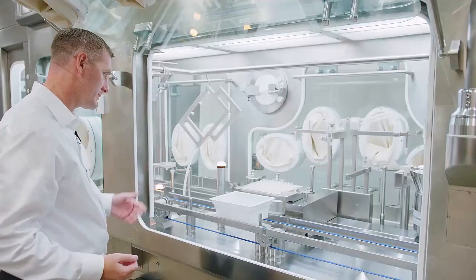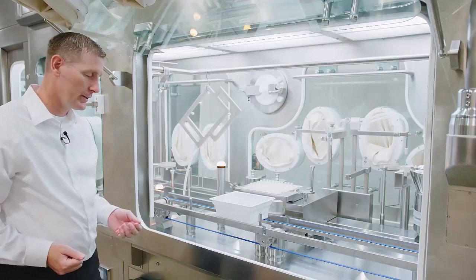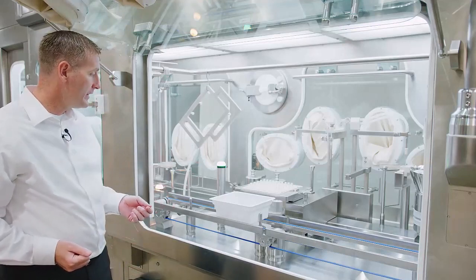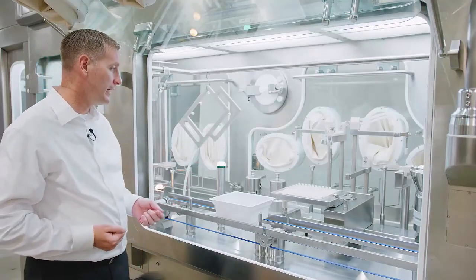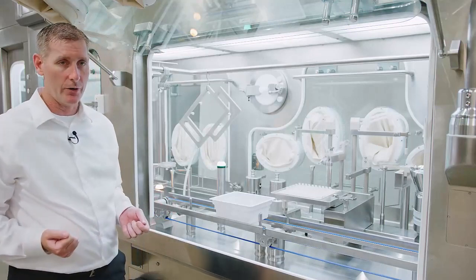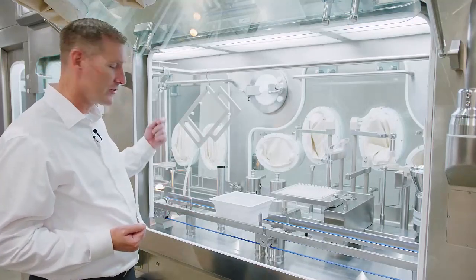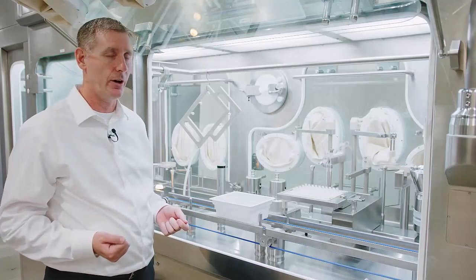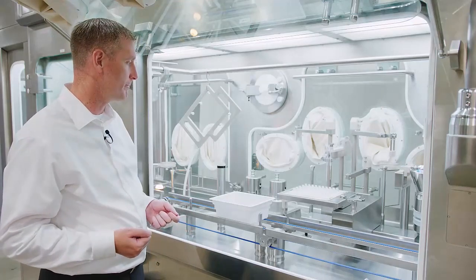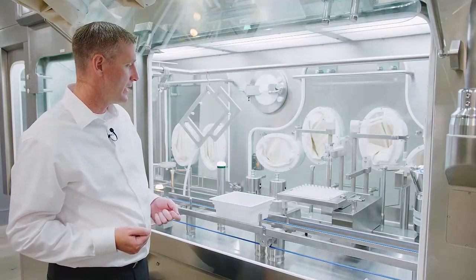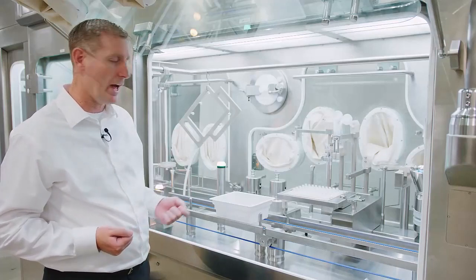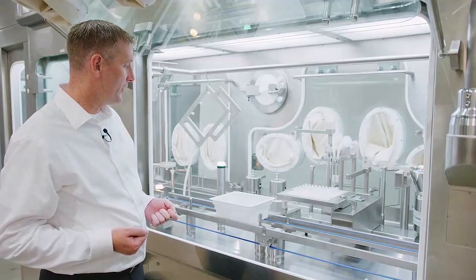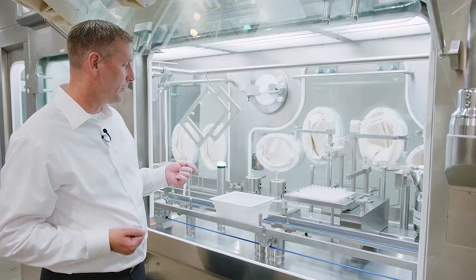And at this point, the system will go and start this particular nest. Now, it's important to also mention that in addition to the manual transfer, AST also offers a robotic automated transfer of this nest on this exact same system. So as you can see here, the fill nozzles, this is a 2-head machine. It will fill the vials from the bottom up.